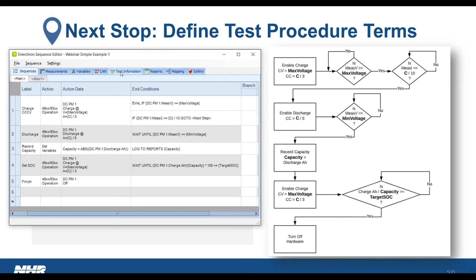If I try to save this program, it's going to give me some warnings. It says the safety tab limit does not contain any items, that the abort sequence does not have any steps, and that I'm using a power module but haven't activated the hardware safety feature inside the power module.